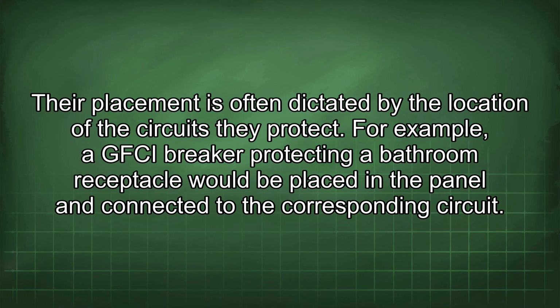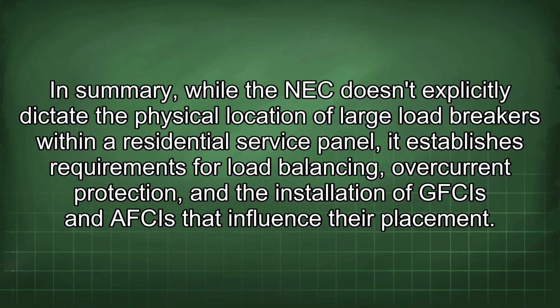For example, a GFCI breaker protecting a bathroom receptacle would be placed in the panel and connected to the corresponding circuit. In summary, while the NEC doesn't explicitly dictate the physical location of large load breakers within a residential service panel, it establishes requirements for load balancing, overcurrent protection, and the installation of GFCIs and AFCIs that influence their placement.